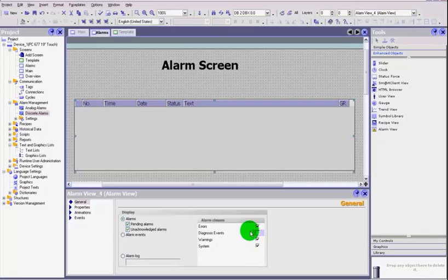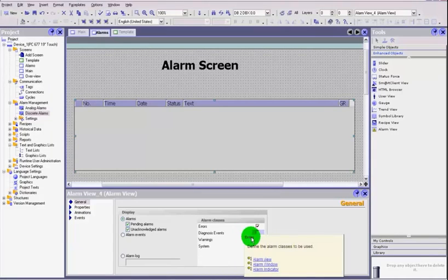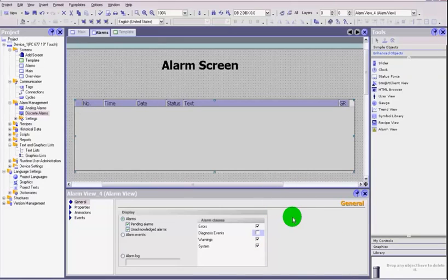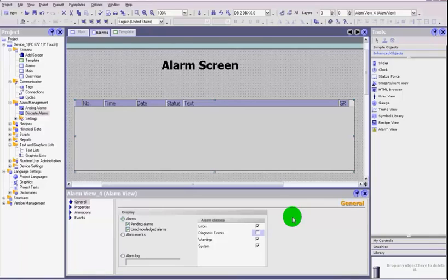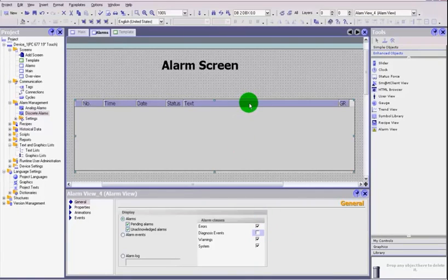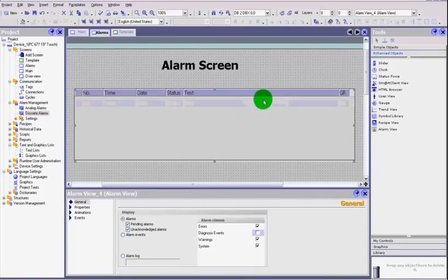Do you want it to show just errors, diagnostic events, warnings, system messages, or everything? When creating a program for operators, you may only want to show errors and warnings. System faults could go on another page out of the operators' reach, so it doesn't get too confusing — any system can have quite a lot of messages. For now, we're going to leave everything checked.